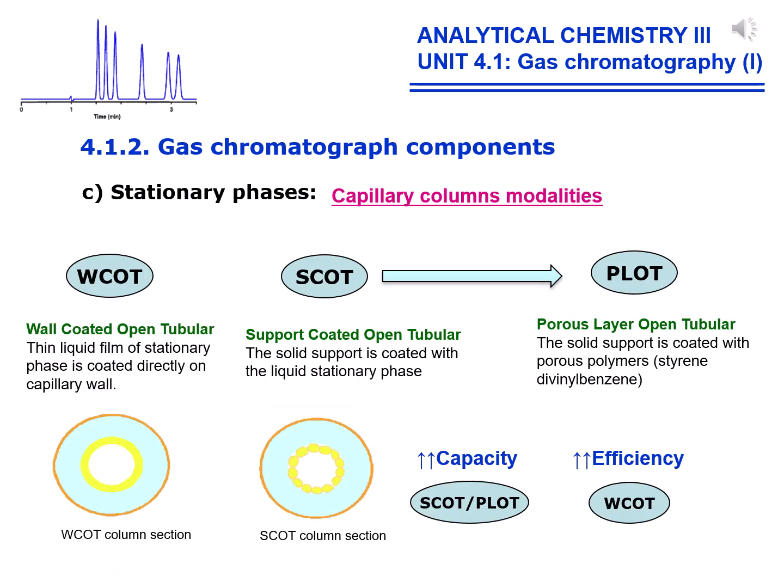Within the capillary columns most commonly used today, there are main types depending on how the stationary phase is immobilized into the capillary. Wall-coated open tubular: these are open tubular columns with coated walls where the liquid stationary phase is spread directly onto the inner wall of the capillary tube. These are the most efficient as the column is empty, and therefore all the diffusion and channel formation problems predicted by Van Deemter don't occur now.